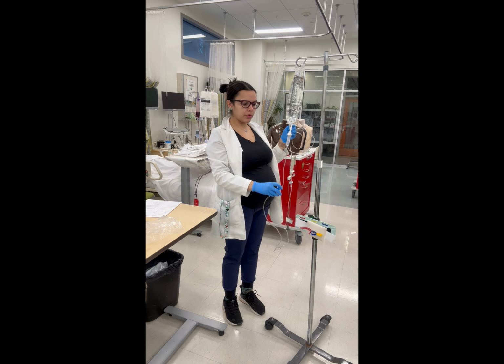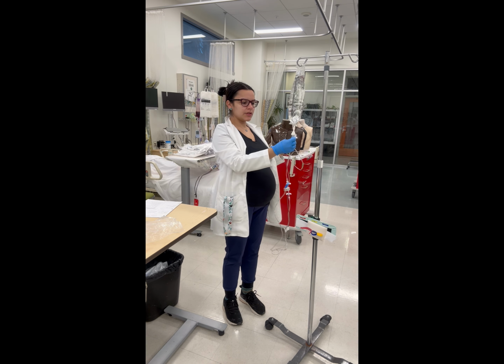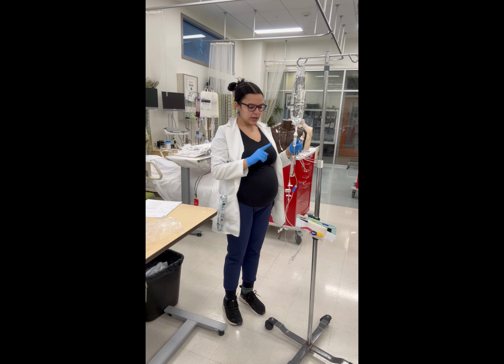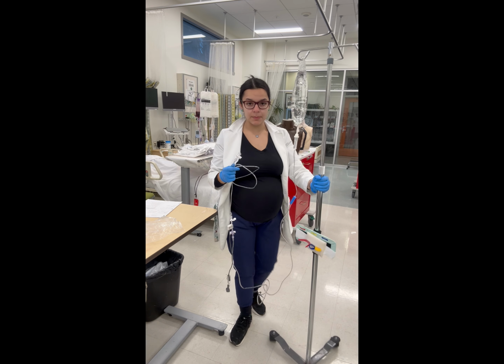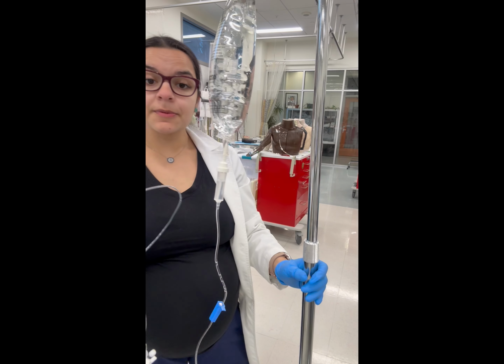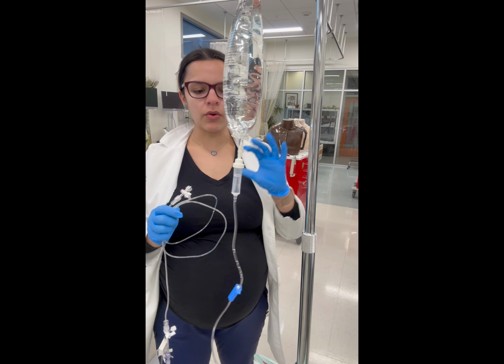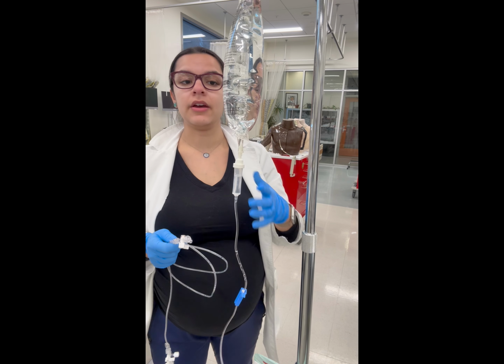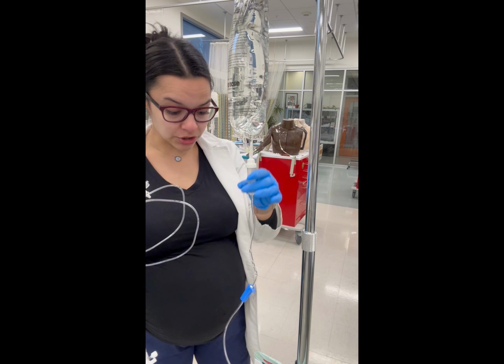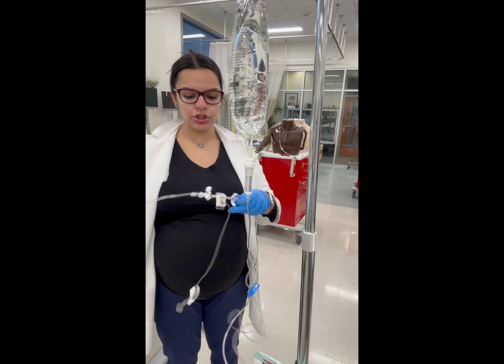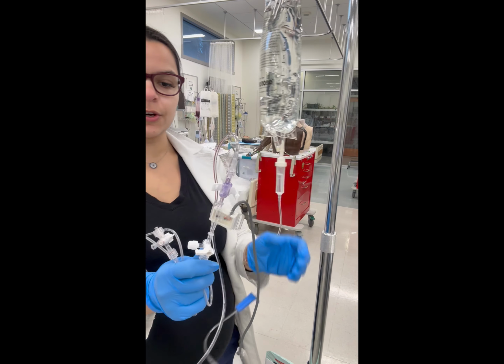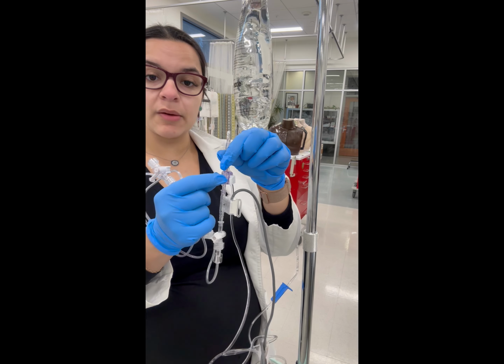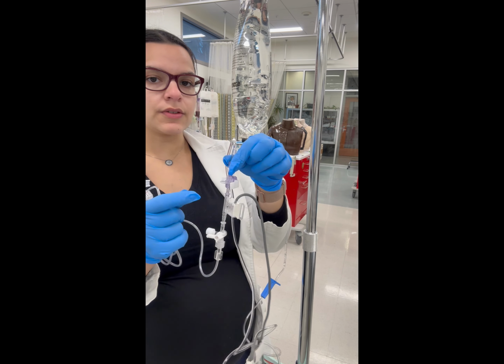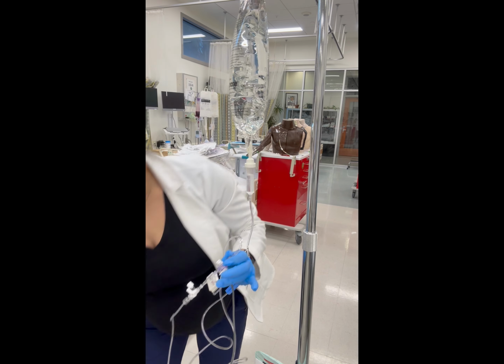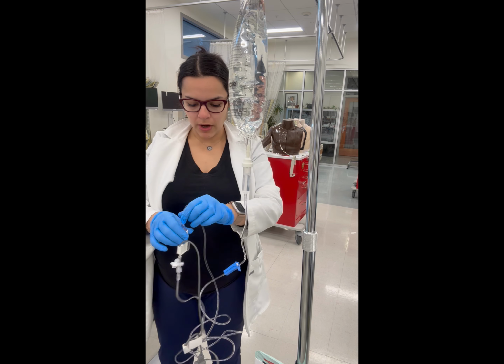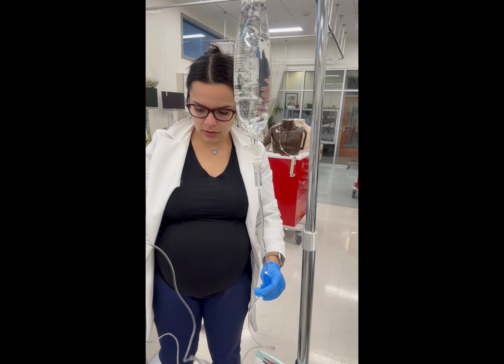So I'm going to open up my roller clamp. I'm going to squeeze my drip chamber about halfway, and I'm going to notice that the flow actually stops, okay? So the flow stops because this is pressurized tubing. So remember, in order to prime this line, we need to flush the line, just like we do once it's attached to the patient, okay? So in order to flush, I'm gonna look down here by my transducer. This is either going to have a pull tab where you flush or a squeeze tab, okay? And that is what I'm gonna wanna use to prime my tubing, okay? I'm gonna go ahead and give that a squeeze.